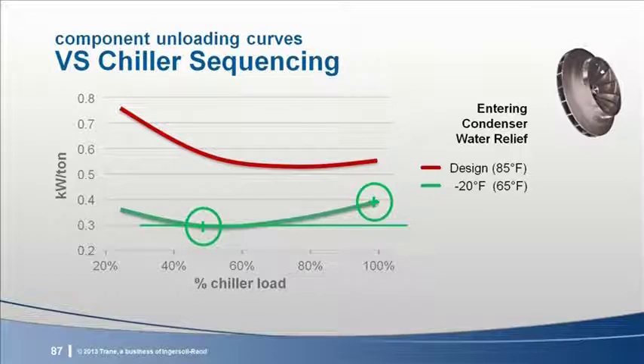Again, it would take a complete system analysis, but with sufficiently reduced lift, it certainly appears that there are times when running 2 variable speed chillers would be better than running 1. The specific chiller's unloading curve, the system design, and other component operating limits combine to make optimally sequencing variable speed chillers a complex task. The challenge is to take advantage of the opportunity while keeping it understandable to the plant operators.